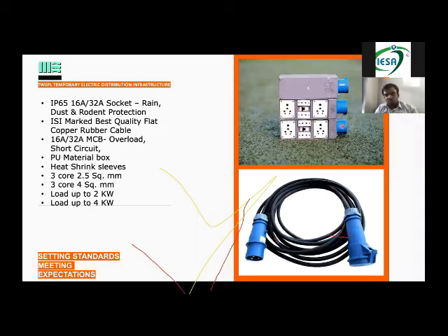These are the single phase sockets. So plug points are single phase. The sockets come in 16 amps and 32 amps. That means 16 amps is around 2 or 3 kilowatts, you can say. So there is a different kind of socket for 1 kilowatt, and 2 pins we have given extra, because if somebody is asking for 2 plug points, maybe they want to charge their mobile, we don't want to lay extra cable. So we've given them 2 plug points also, no problem, you can charge your mobile as well. So all these things are separate.